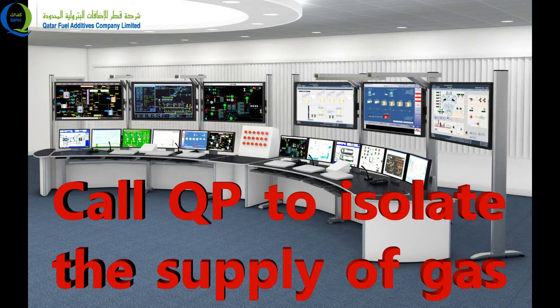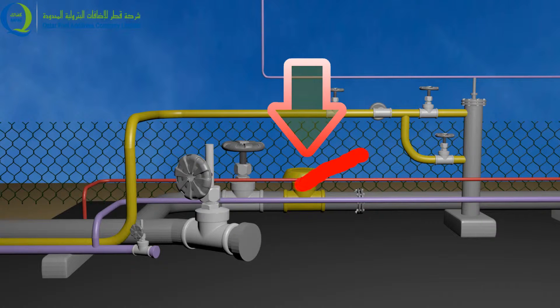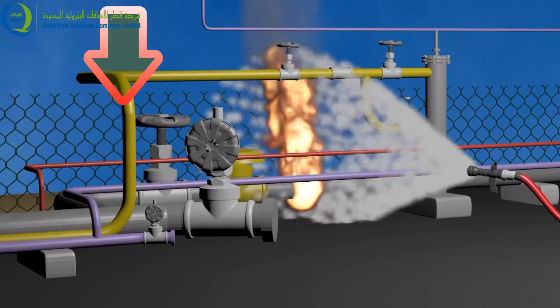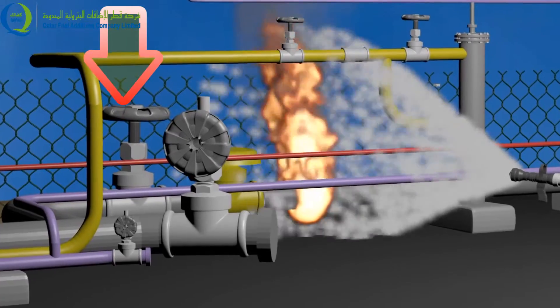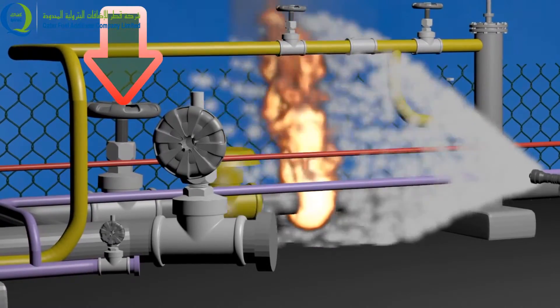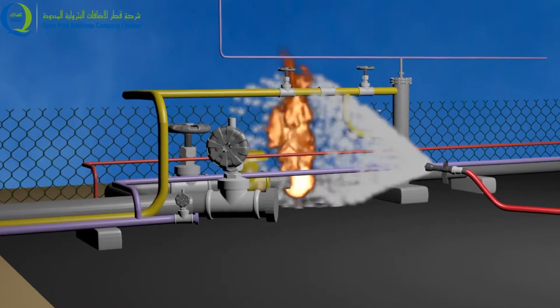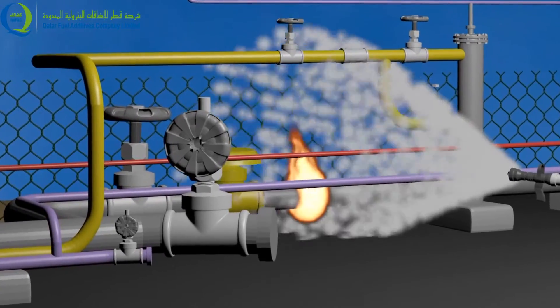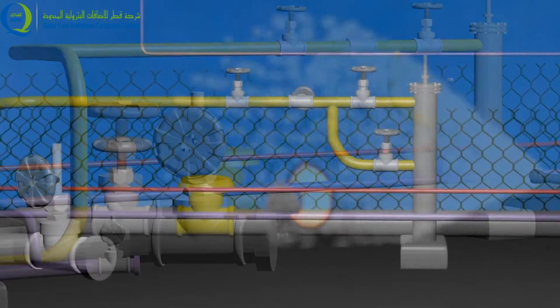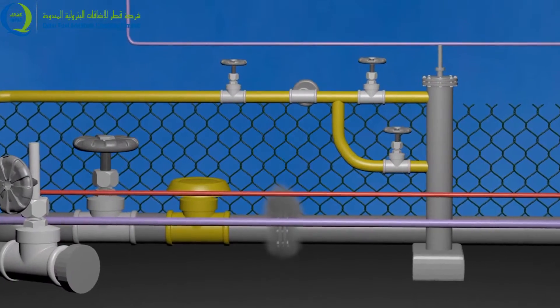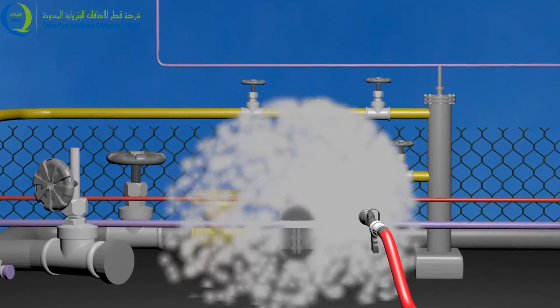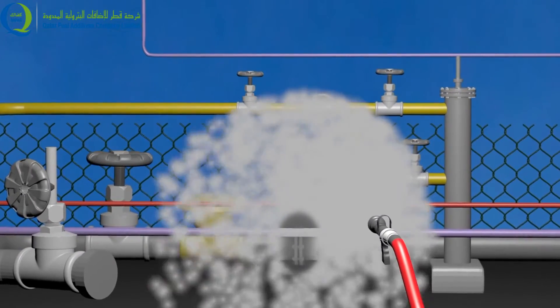The best way to control this type of fire is to isolate the gas supply. Contact QP to stop the gas supply. Isolate the UV remotely, cool the area, and close the local manual valve with the protection of a water shield. After control of the pressurized flame, residue leaking gas may ignite again. Suppress the unburned leaking gas with water and keep cooling the area until the gas supply has been completely isolated.